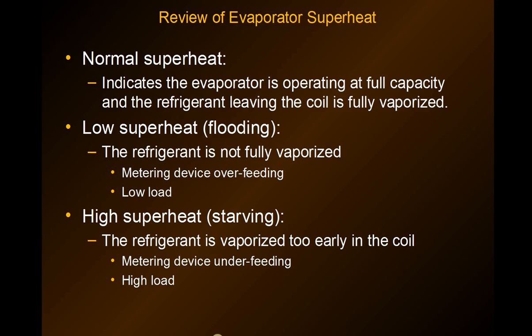Low superheat, called flooding, is when not all the refrigerant is turned into vapor in the evaporator. That either means you have an overfeeding metering device or a low load condition. High superheat, called starving, means the refrigerant vaporizes way too early in the evaporator coil, resulting in very poor cooling inside the device.